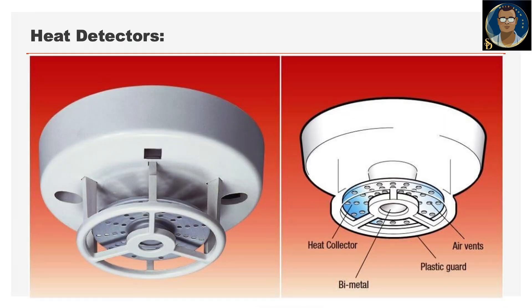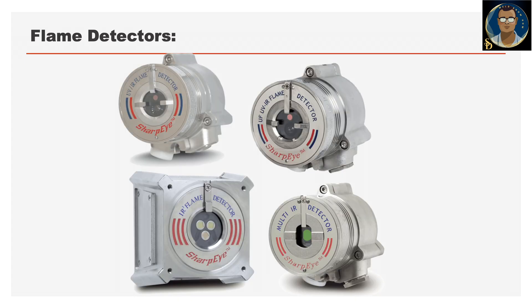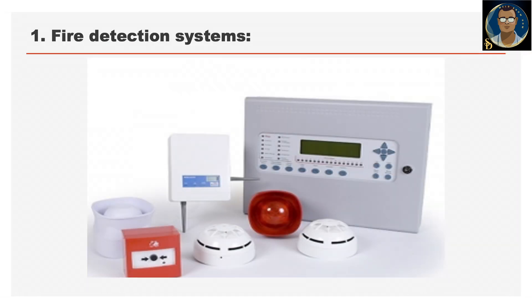Heat detectors are activated when a specific temperature threshold is exceeded, indicating the presence of fire. Fixed temperature heat detectors respond to a constant temperature, while rate-of-rise heat detectors trigger alarms based on the rate at which the temperature increases. Flame detectors use sensors to detect the presence of flames, providing additional confirmation of a fire event. Fire alarm control panels receive signals from detectors and activate audible and visual alarms to alert occupants to evacuate the building or facility.